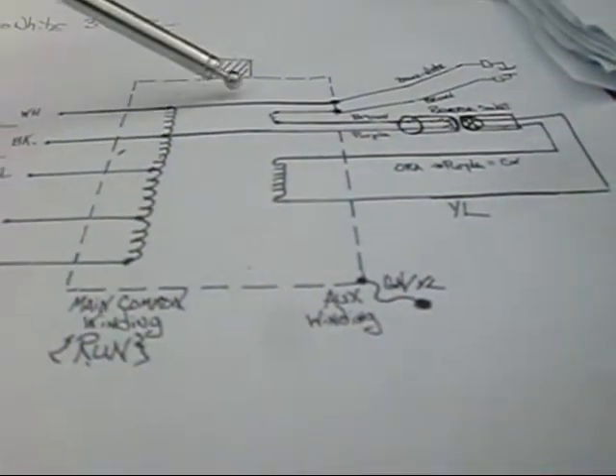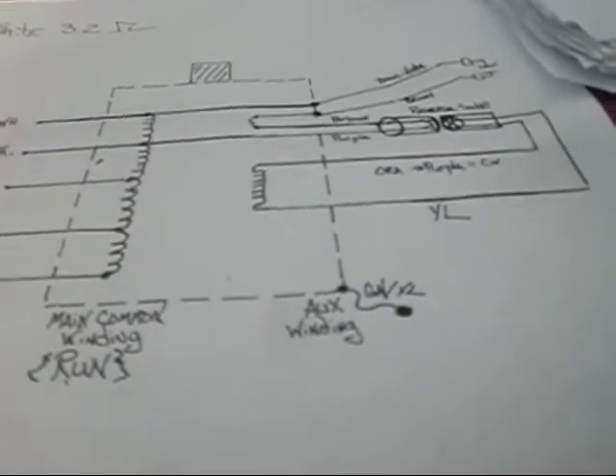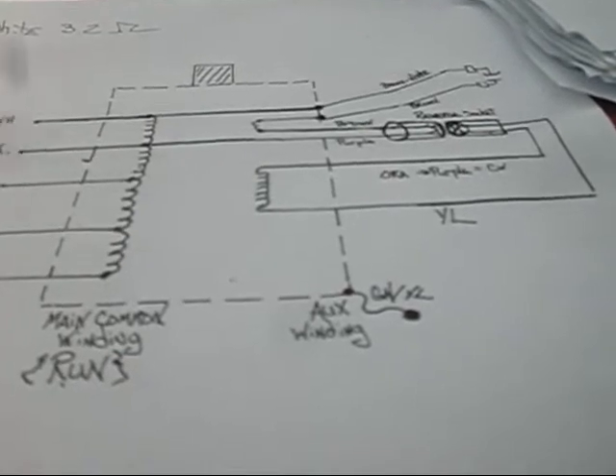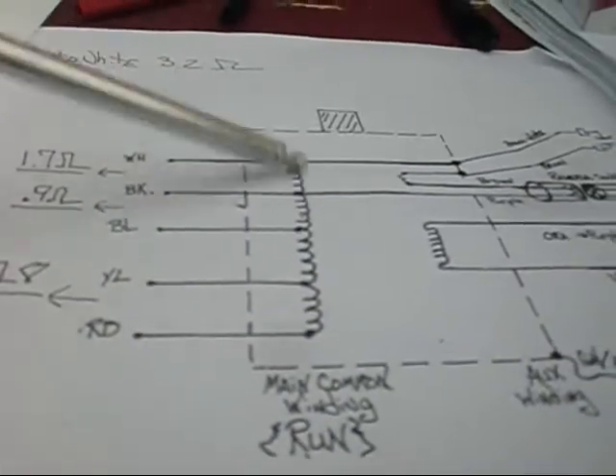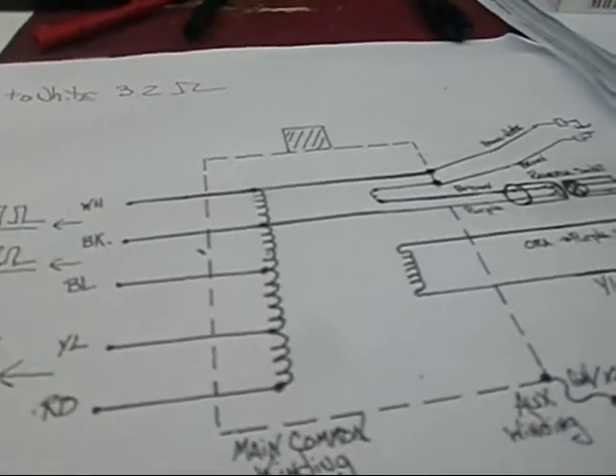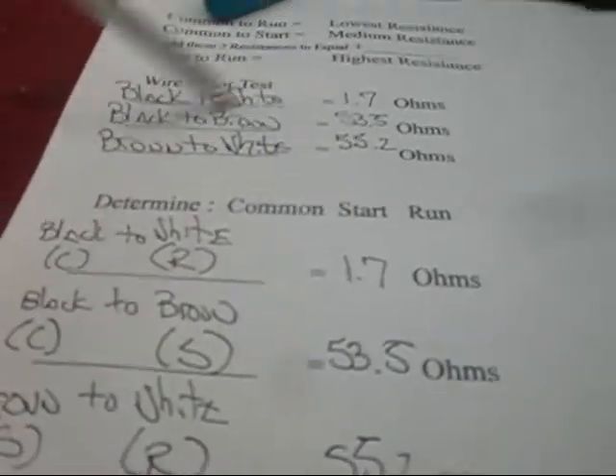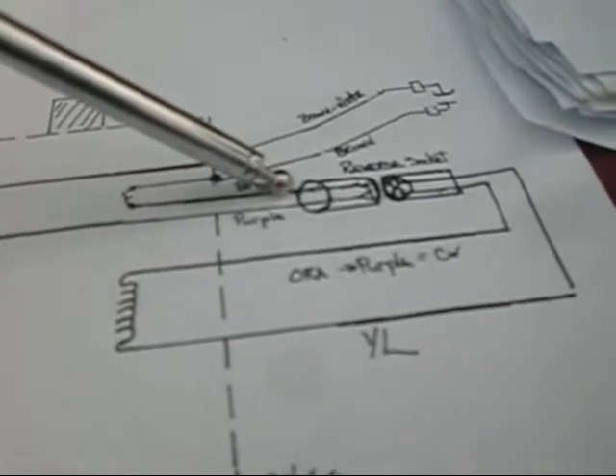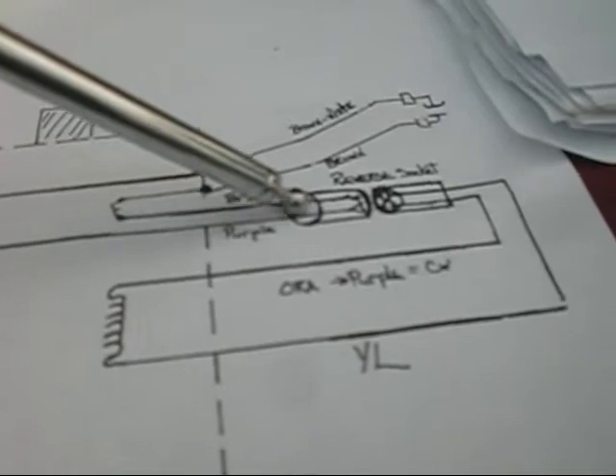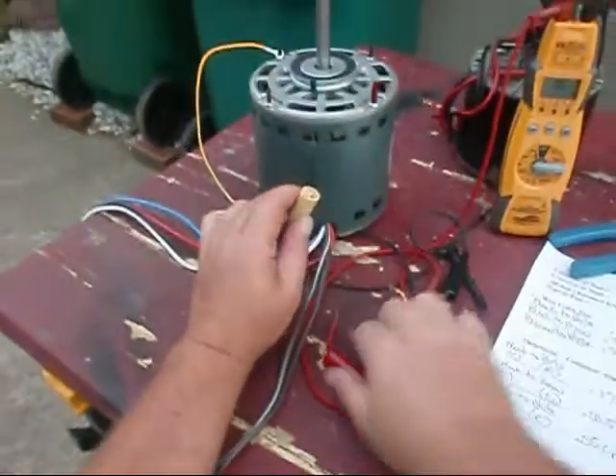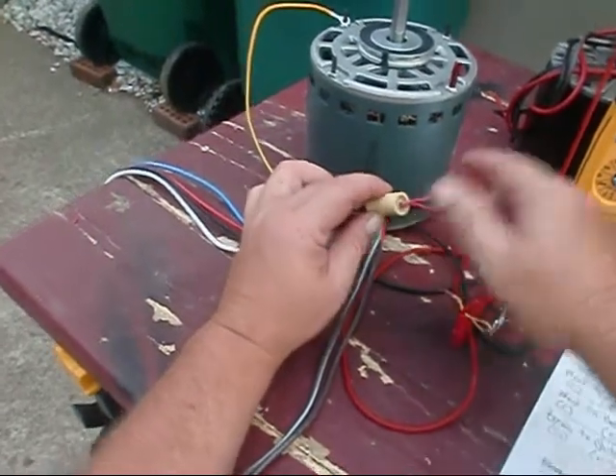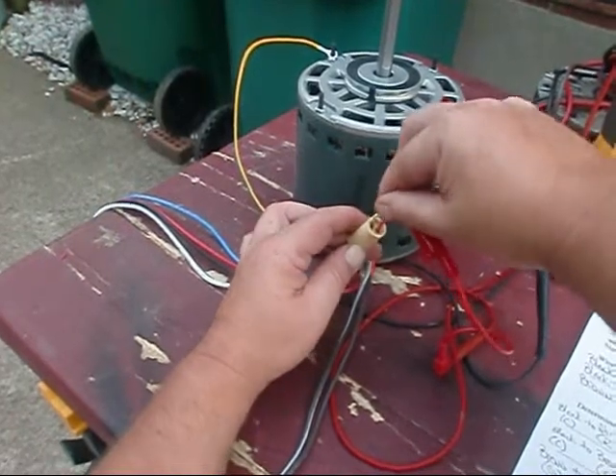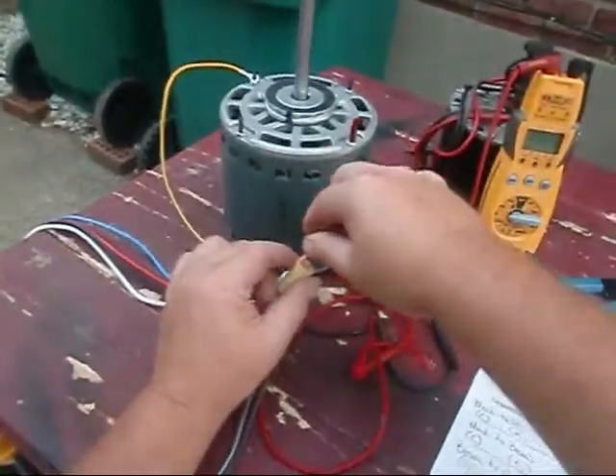Let's test this real quick. Do you know what auxiliary windings are? Do you care what auxiliary windings are? Our buddies do. Alright guys, we're going to get back after it. So what we did was we determined our brown and our white to our black gave us 1.7. And that's what determined that our brown and white wire was also a run winding. White is run winding. Black is run winding. Blue is run winding. Yellow, if we had one, is run winding. And red is run winding. We determined also that our brown is our start from our tests. So what we're going to do right now is we're actually going to test our clockwise, counterclockwise module. We're going to break it loose if we can. I've already rigged up some doodahs here. We're going to plug it into our female side of our doodah.